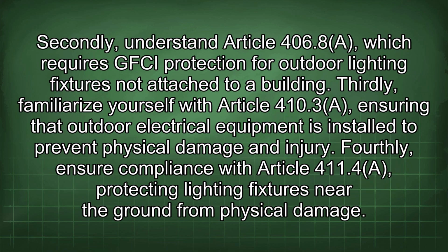Secondly, understand Article 406.8a, which requires GFCI protection for outdoor lighting fixtures not attached to a building. Thirdly, familiarize yourself with Article 410.3a, ensuring that outdoor electrical equipment is installed to prevent physical damage and injury. Fourthly, ensure compliance with Article 411.4a, protecting lighting fixtures near the ground from physical damage.